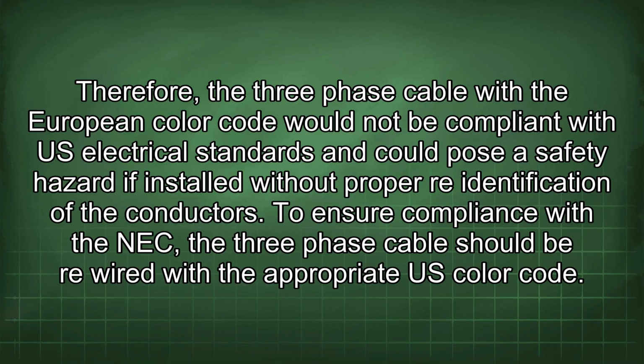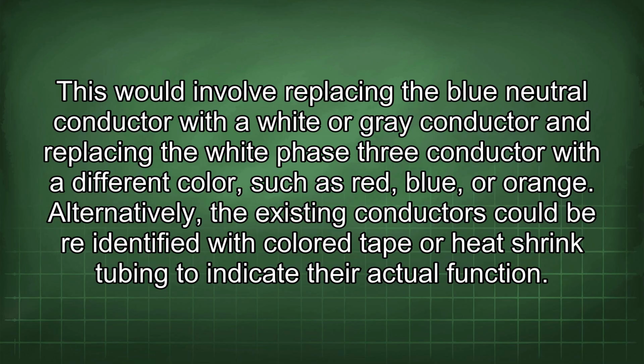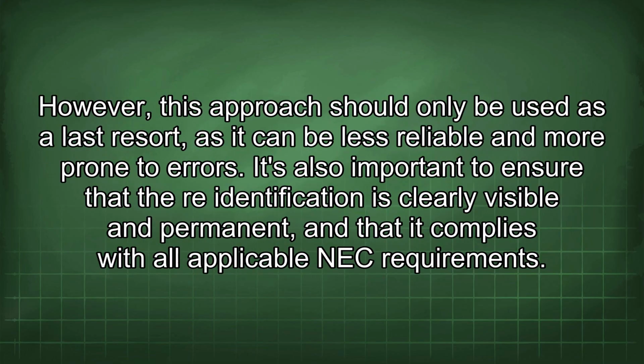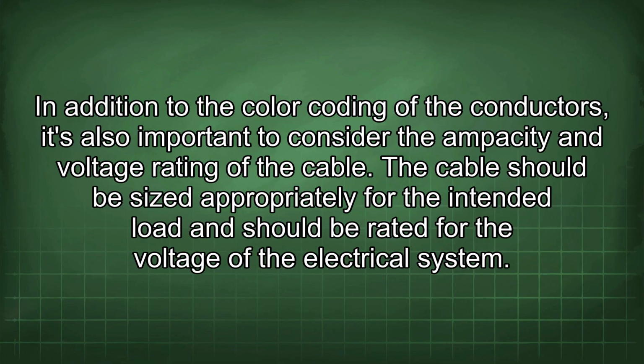To ensure compliance with the NEC, the three-phase cable should be rewired with the appropriate US colour code. This would involve replacing the blue neutral conductor with the white or grey conductor and replacing the white phase 3 conductor with a different colour, such as red, blue, or orange. Alternatively, the existing conductors could be re-identified with colour tape or heat shrink tubing to indicate their actual function. However, this approach should only be used as a last resort, as it can be less reliable and more prone to errors. It's also important to ensure that the re-identification is clearly visible and permanent, and that it complies with all applicable NEC requirements. In addition to the color coding of the conductors, it's also important to consider the ampacity and voltage rating of the cable.